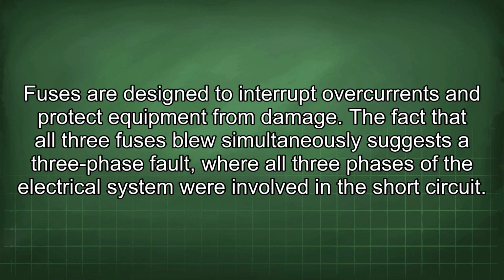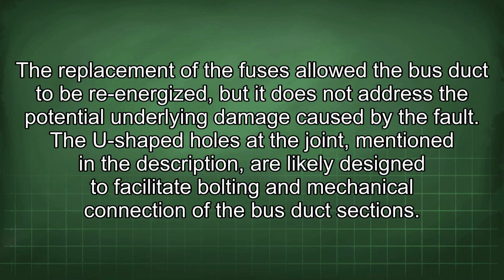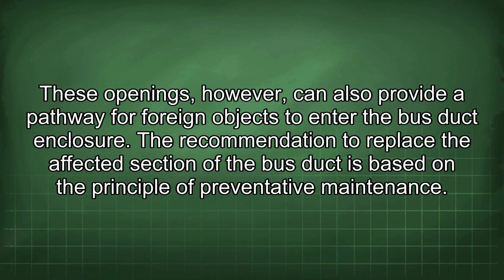Fuses are designed to interrupt overcurrents and protect equipment from damage. The fact that all three fuses blew simultaneously suggests a three-phase fault, where all three phases of the electrical system were involved in the short circuit. The replacement of the fuses allowed the bus duct to be re-energized, but it does not address the potential underlying damage caused by the fault. The U-shaped holes at the joint mentioned in the description are likely designed to facilitate bolting and mechanical connection of the bus duct sections.